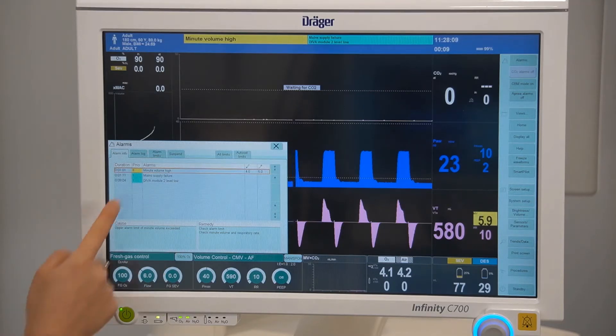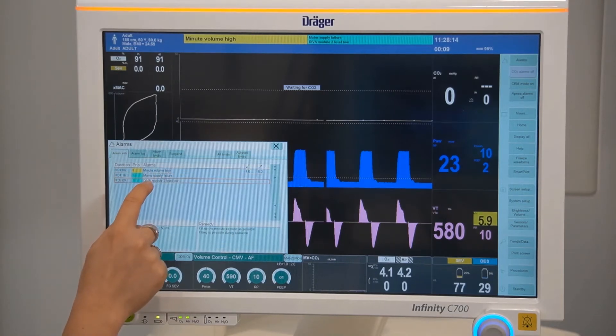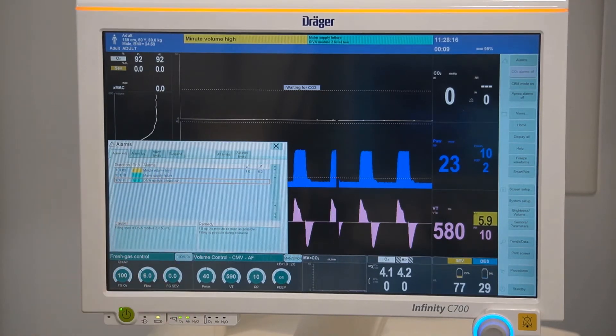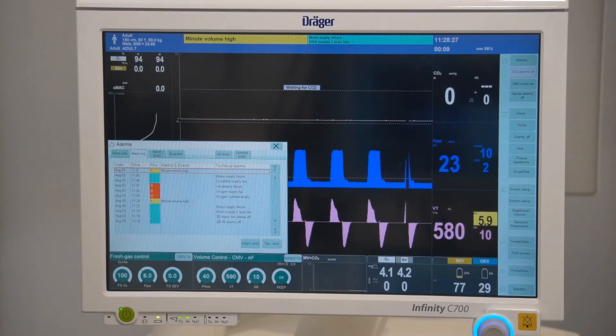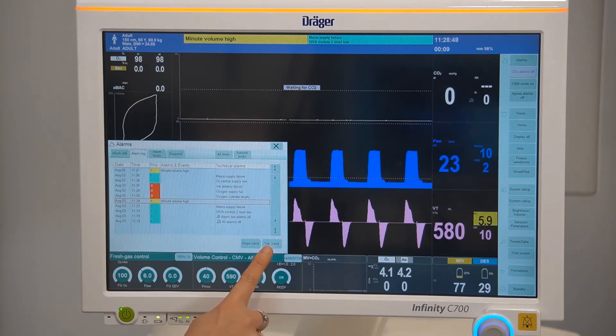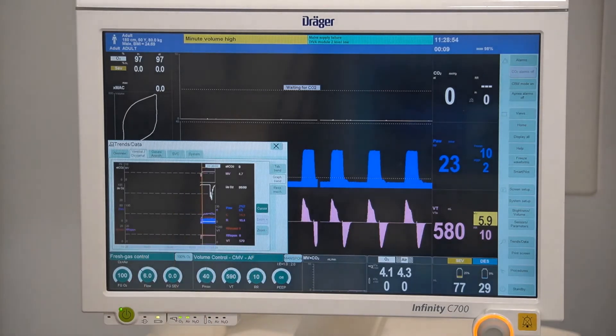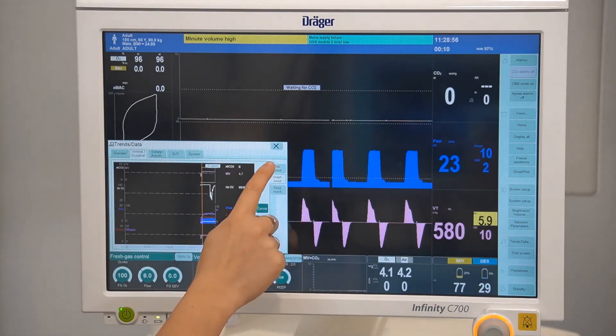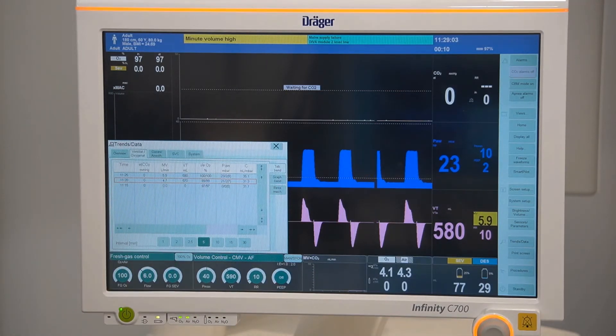If there are multiple current alarms, highlighting the desired alarm will bring up the desired message. Alarm log will display a list of all the alarms that have been triggered during the course of the case. By selecting graph trend or tabular trend, this will open up the trend display as either curves or as a table at the time of the selected alarm.